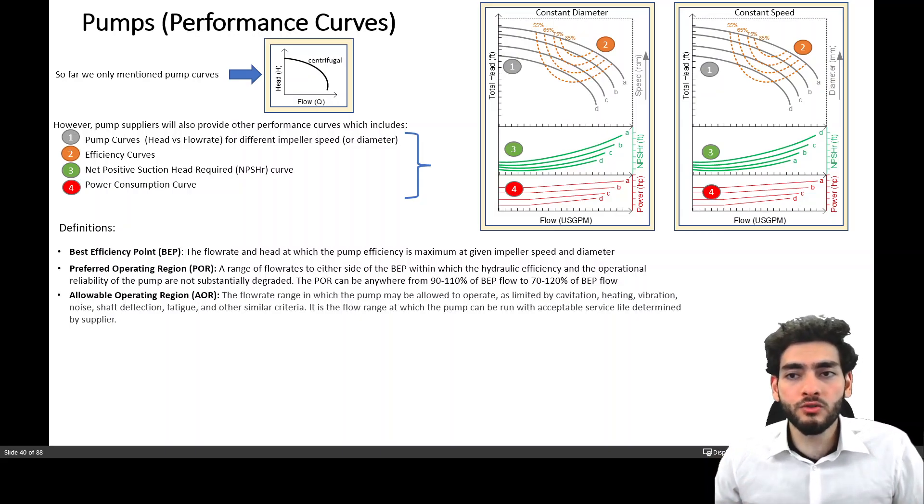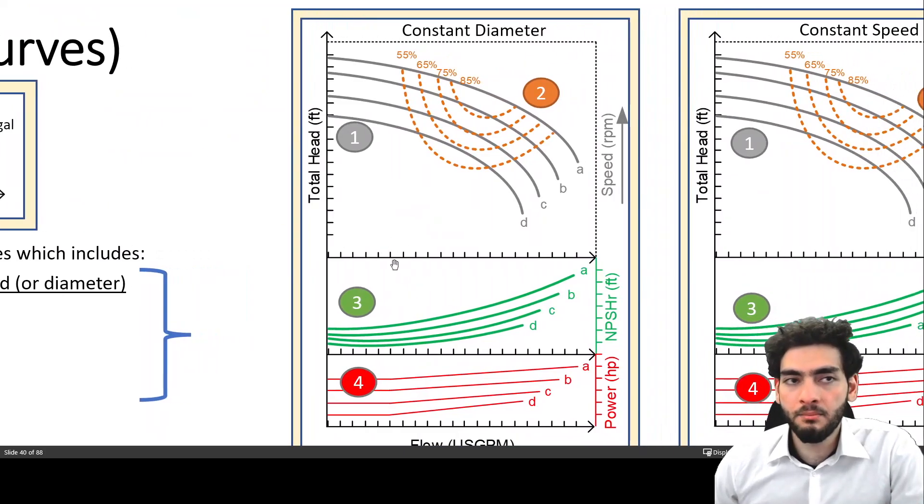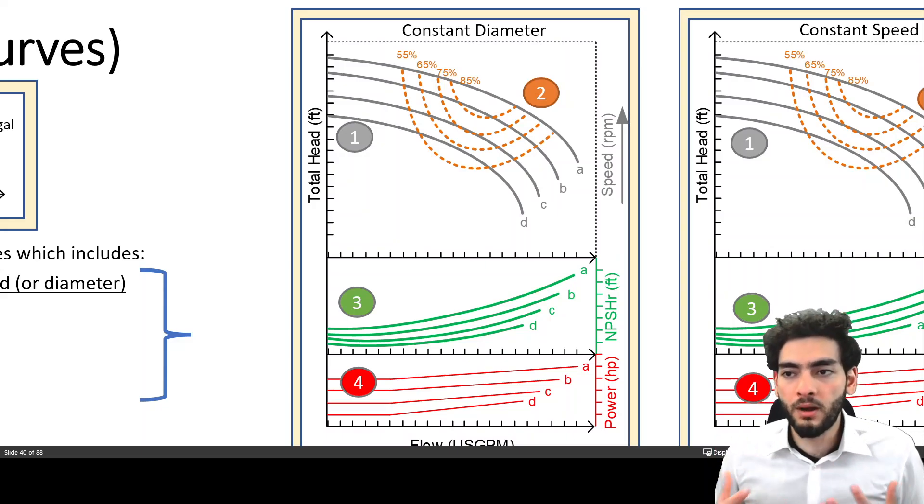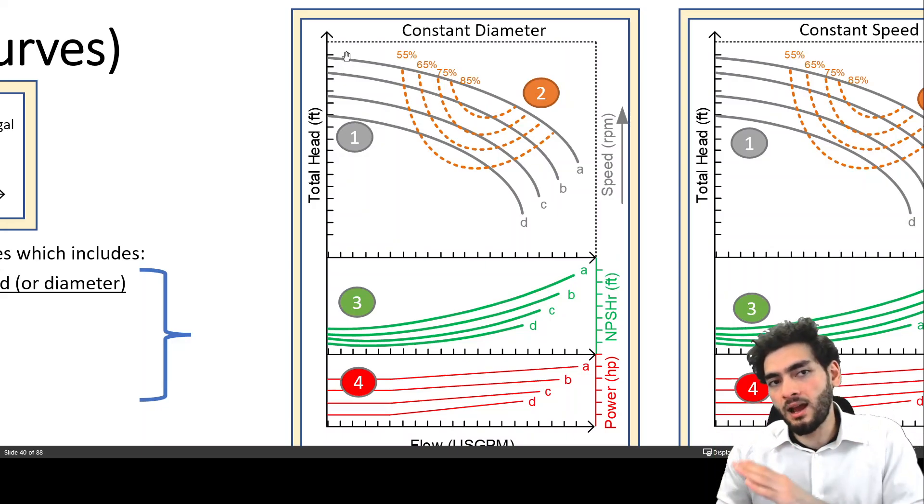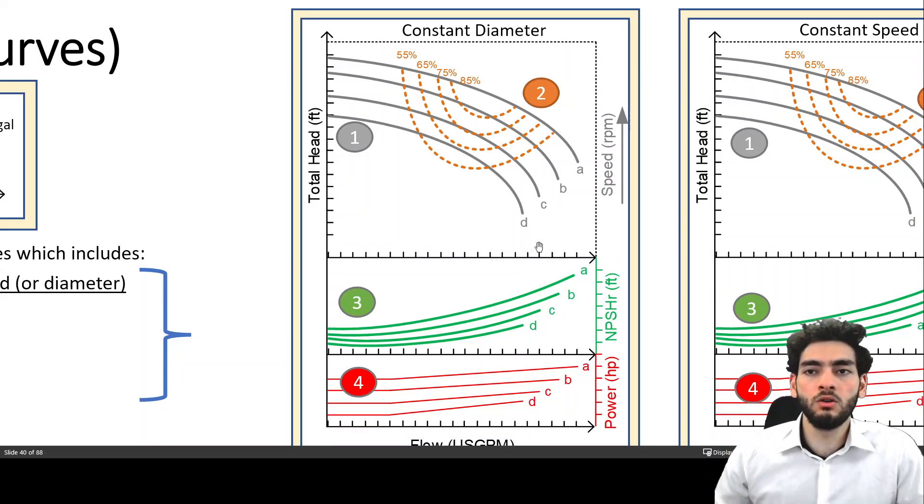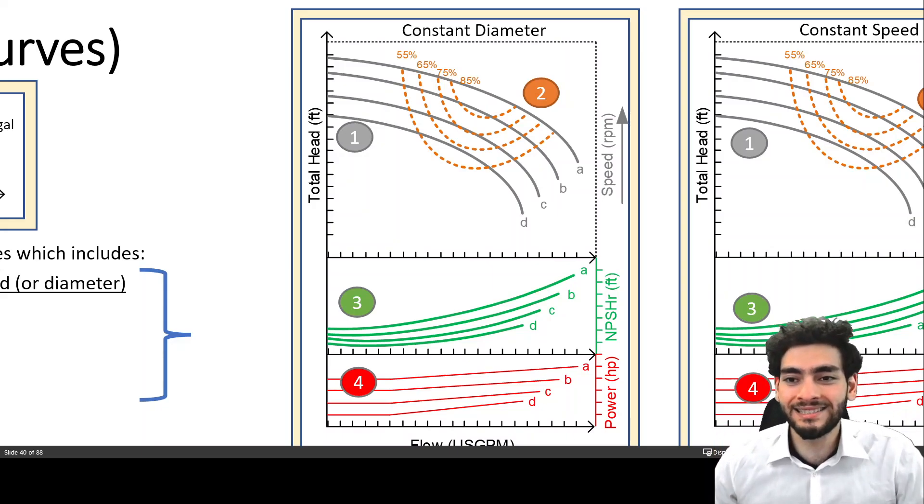So this is a flow rate that the pump supplier will be providing you and he might say never ever run the pump below maybe half a gallons per minute because if you do that then you are essentially damaging your pump. And he will give you like a lower end and then a higher end as well so maybe you never ever want to increase beyond a particular flow rate because then you're also susceptible to damaging the pump. And this number is provided to you by the supplier based on testings that they have done.